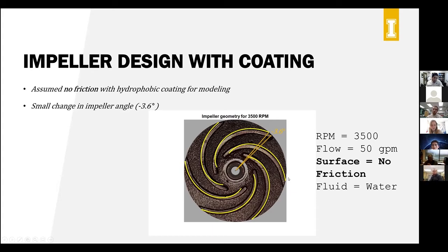So to be honest, we were a little surprised that the angle change is just a little bit, 3.6 degrees. We were hoping for more angle change for a frictionless surface, but looking at the equation and what's going on, it turns out that most of the force on the water is for acceleration, not from the friction. So friction plays just a little bit of the overall head loss, and most of the power is imparted as an acceleration.